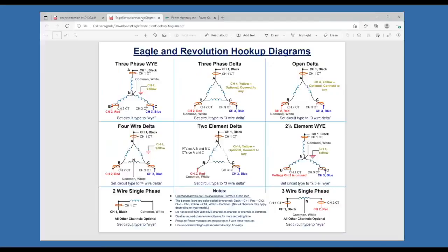Let's go ahead and take a look at the Eagle and Revolution hookup diagram. And you can see, again, in Provision, you'll be initializing the recorder, and you would set it up for a Y circuit type, which is the default. That is phase to neutral voltages. If you have a 4-channel recorder, that yellow voltage lead is optional. And they are sealed inside, so you don't have to worry about water getting in them.